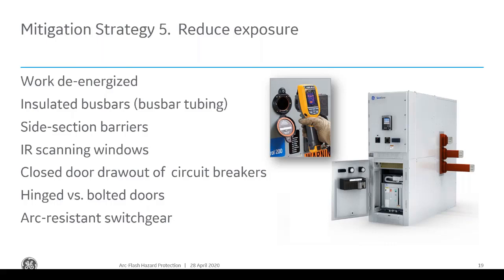Obviously, always work on de-energized equipment if possible. Make sure your insulation and conductors are sized properly and spaced properly. Use mechanical designs with IR scanning windows, so you can check that you don't have any arcing going on before you do any switching or start to work on a piece of equipment. Hinged versus bolted doors, and obviously arc resistant switchgear, which I talked about earlier. So there are a number of ways to reduce your exposure here.